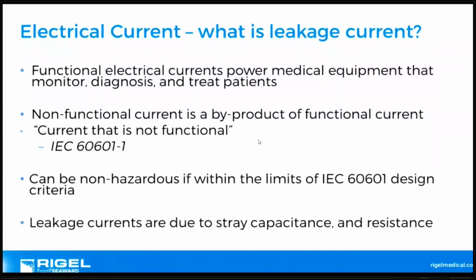Anyway, functional current and leakage current. So what is leakage current? Well, functional current powers the device. So if you've got a wattage setting on the medical equipment, let's say it takes 100 milliamps to power the whole system. Well, 100 milliamps might flow through the live or hot conductor, but only 99 might flow through the neutral. So this non-functional current, i.e. leakage current, is escaping the system.